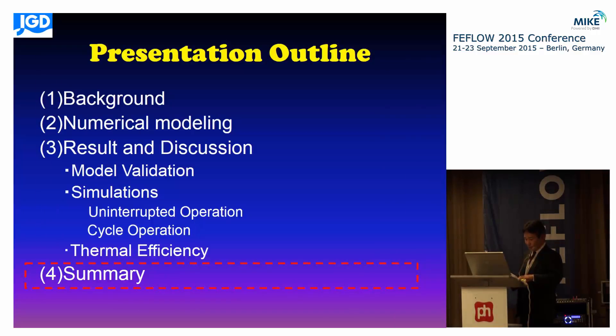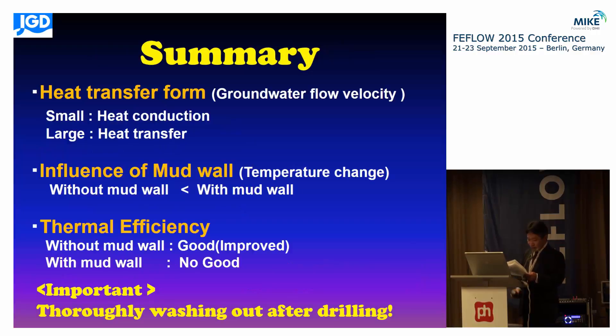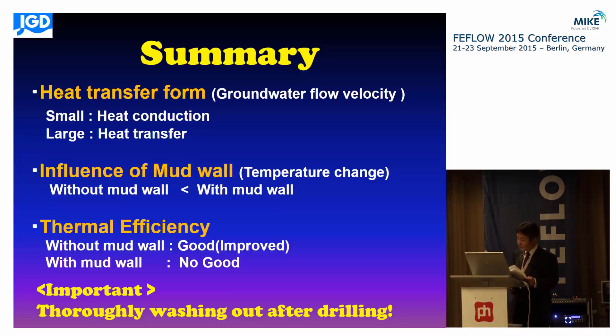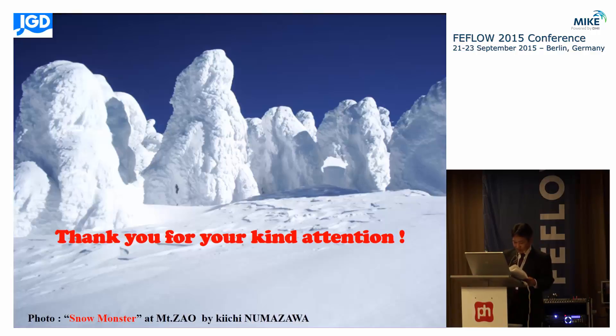I would like to move on to the final part of my presentation: the summary. Here I have summarized the key points. First, when the groundwater flow velocity is small, thermal energy movement is dominated by heat conduction. Second, if the mud wall remains, it brings thermal influence and becomes a thermal resistance. When a vertical borehole is built, it is recommended to thoroughly wash out any mud on the borehole wall in order to make the ground heat extraction system as efficient as possible. Thank you very much.